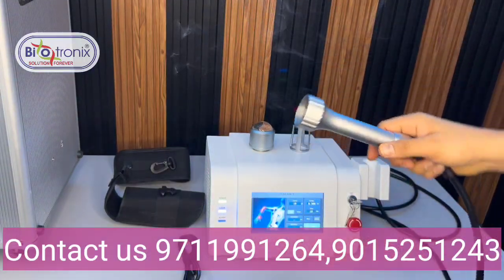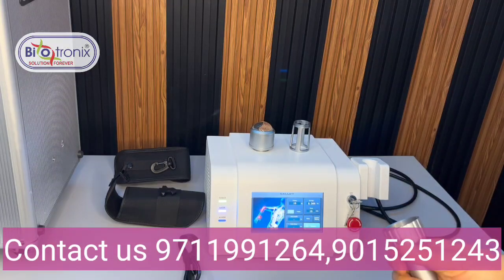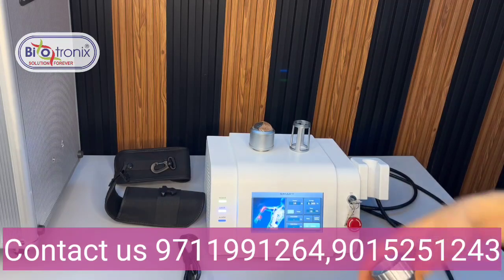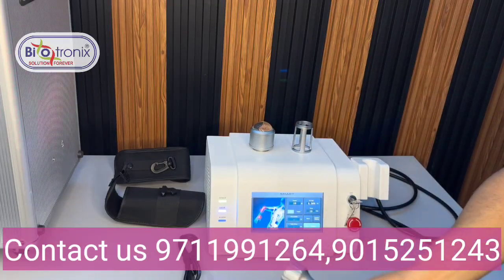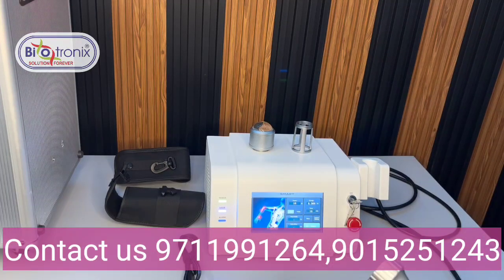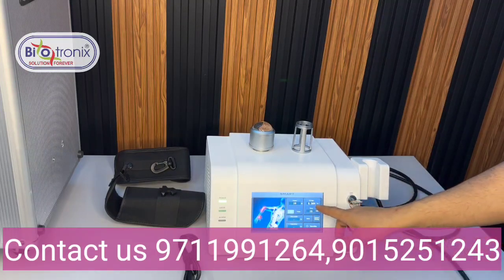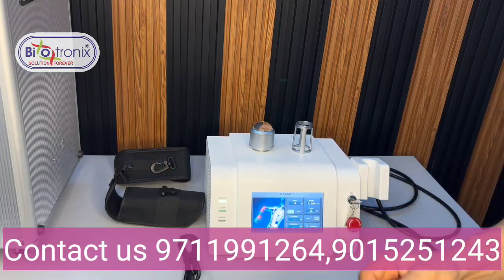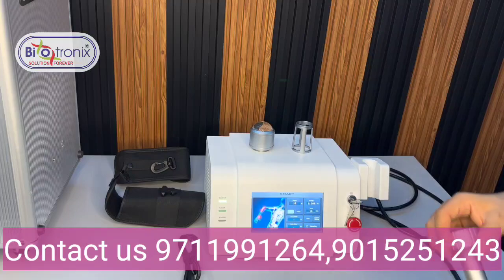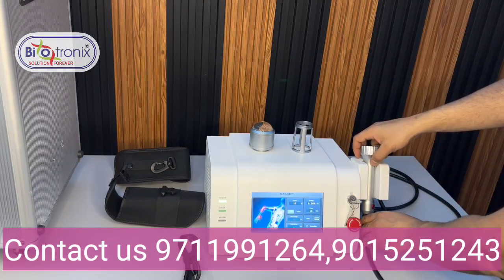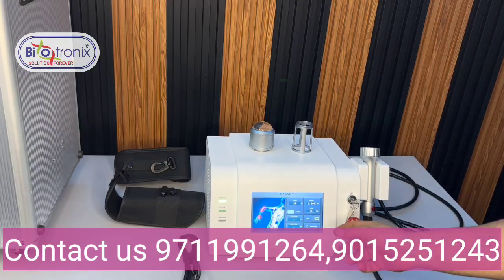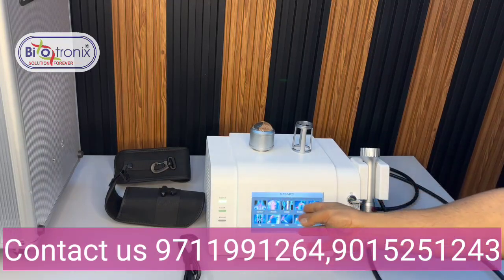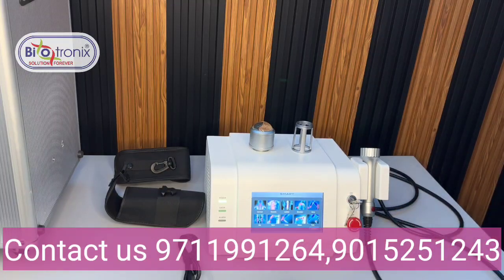So this is the power and the intensity of the laser, and you can see it was the maximum 10 watt. The doctor can use less if the patient feels discomfort with the heat, or the doctor can use that attachment if the patient feels too much heat. Because this is a hot, high intensity laser, you will have to face the heat, so according to that, the doctor can adjust the power and all. So now I switch it off. This is the energy I have got while using it on my hand. So this will be calculated and shown over here. So this was the demo for the device. This is the class 4 laser, 10 watt, 980 nanometer, and now I go back, and these are the various other treatment areas you can select. So thank you for watching.